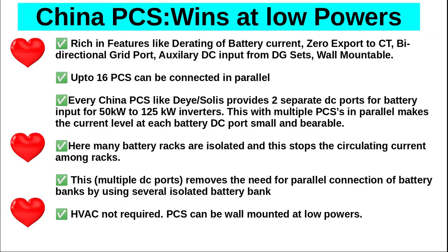When I say China PCS, for example, from Deye or Solis, up to 16 PCSs can be connected in parallel. Every China PCS like Deye or Solis provides 2 separate DC ports for battery input for 50 kilowatt to 125 kilowatt inverters. This, with multiple PCSs in parallel, makes the current level at each battery DC port small and bearable.